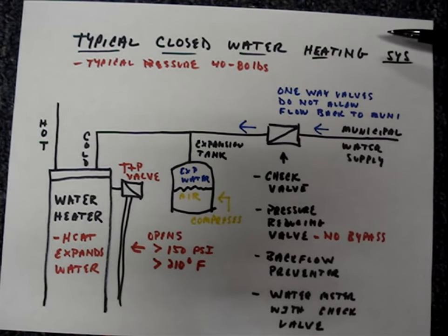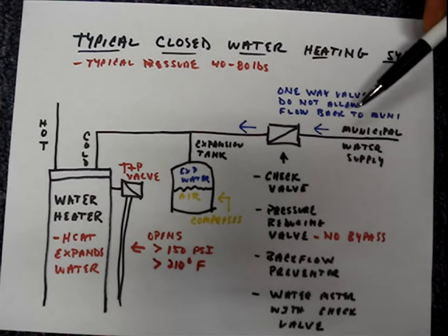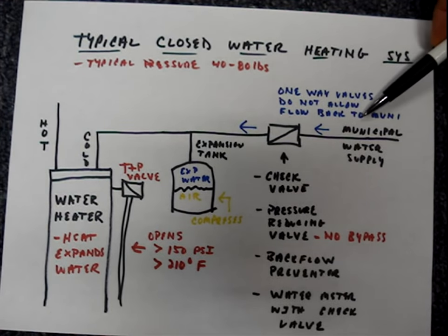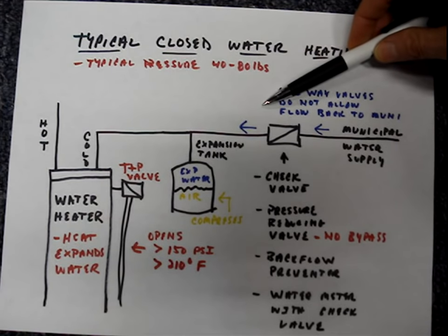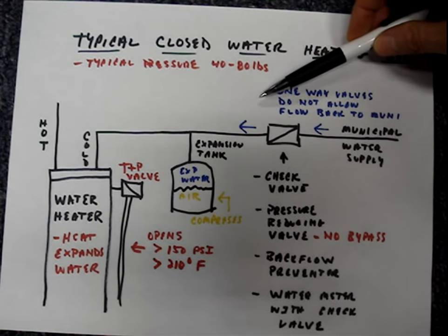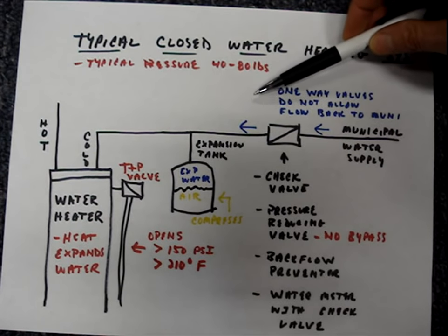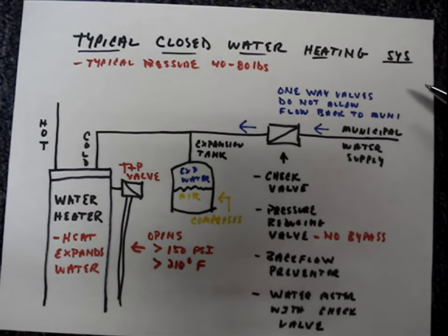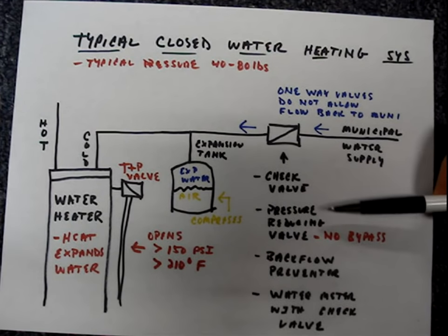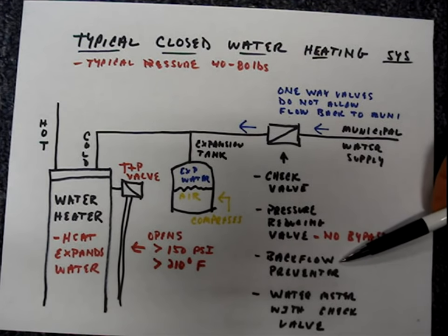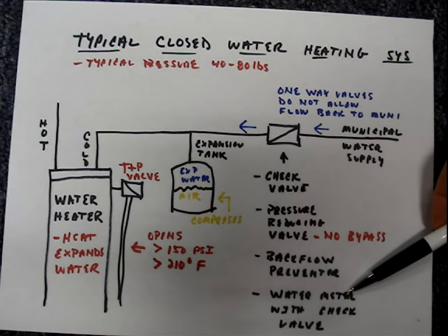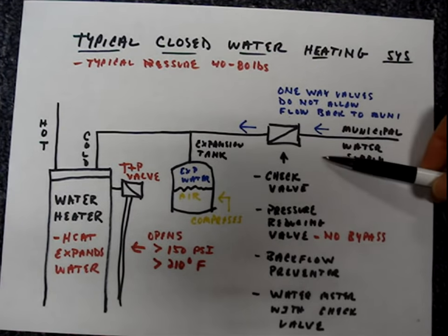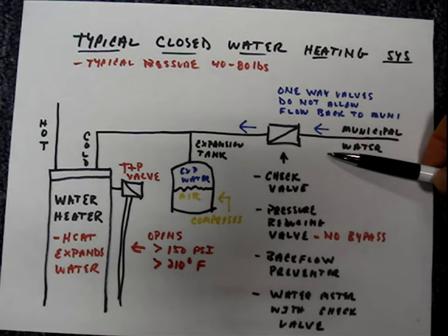A closed water heating system has a one-way valve. The valve allows water to flow from the municipal water supply and into your home's water system. If working properly it won't allow water from your home's water system to flow back into the municipal supply. The one-way valve could be a check valve, a pressure reducing valve with no bypass, a backflow preventer, or a water meter that has a check valve contained in it. Typically you'll find one of these valves located where the water flows into your home, somewhere near the water meter.